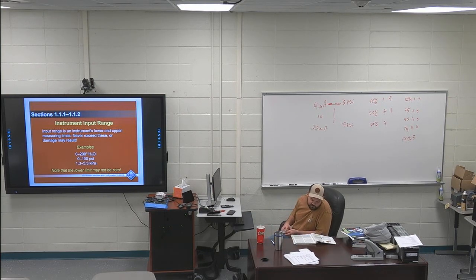For example, if an instrument has a range of 60 to 400 inches of water, the 50% point of the span is not 170 inches of water, because the zero value, the minimum value of the range, is 60 and not 0 inches. In this case, add the calculated 50% span point to the zero value to determine a true 50% point. So 170 plus 60 equals 230.